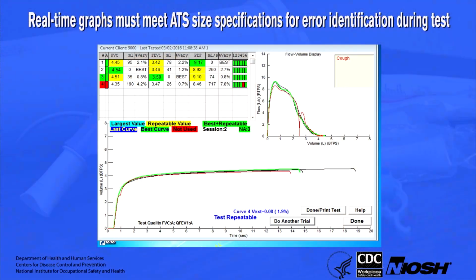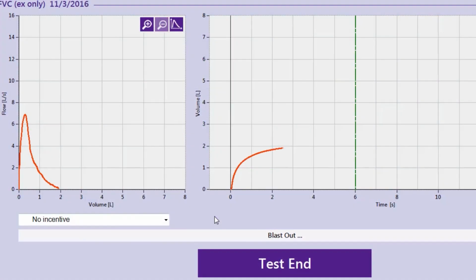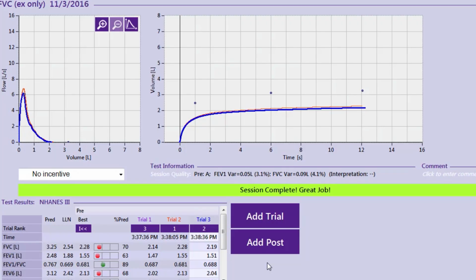Spirometry systems need to provide real-time graphical displays for use by the technician during the test. They need to display both volume time and flow volume graphs. Spirometry software needs to have computer-derived technical quality indicators, including a dedicated routine for verifying spirometer calibration. It is recommended that software store at least 8 maneuvers within one test session. Both volume time and flow volume graphic results need to be stored from at least the 3 best maneuvers. Preferably, the spirometer needs enough memory to save all the maneuvers from one testing session.